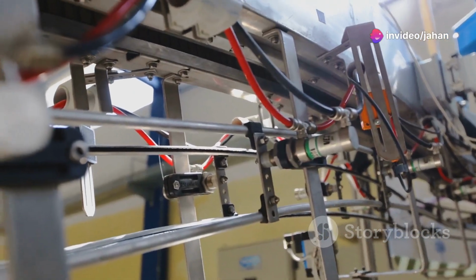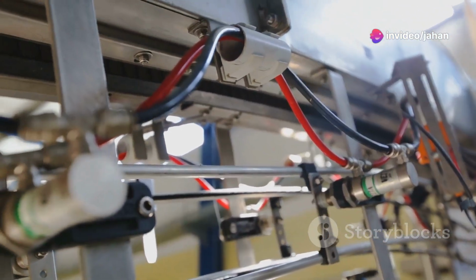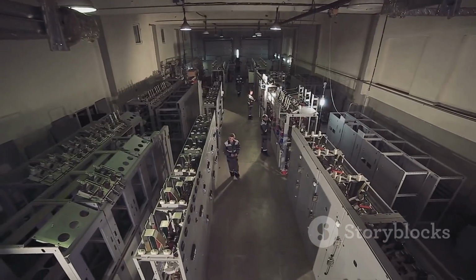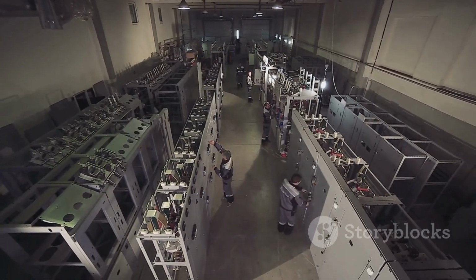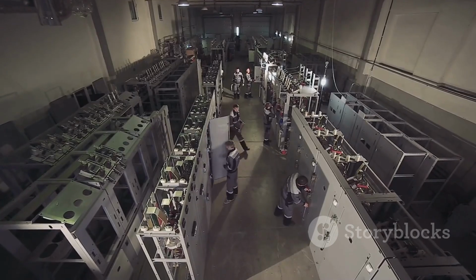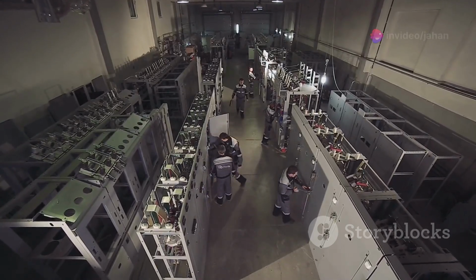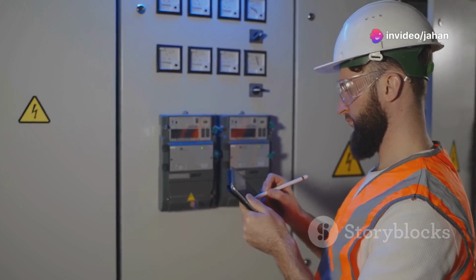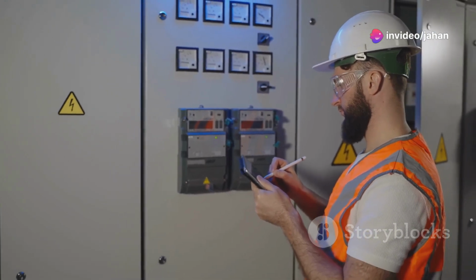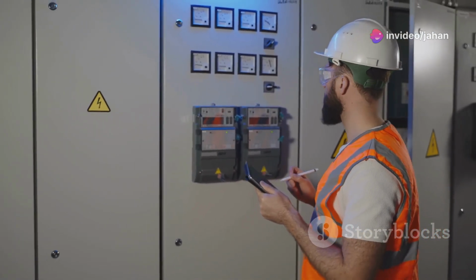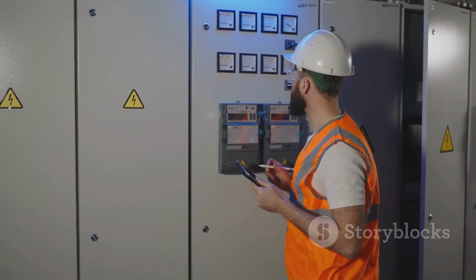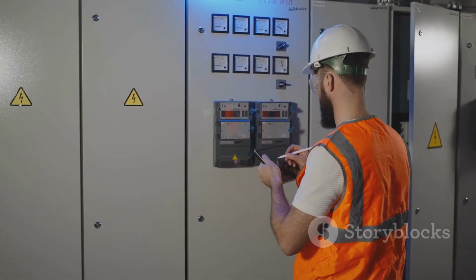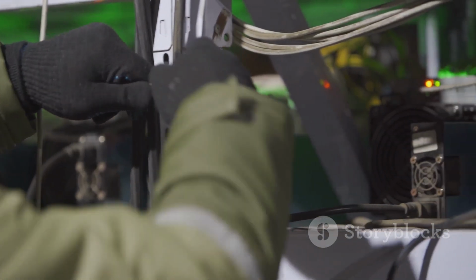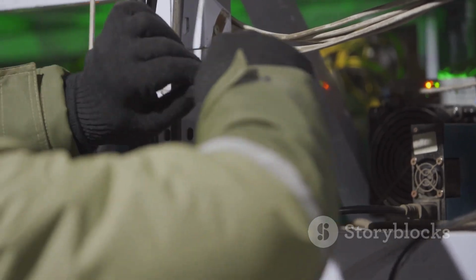Well, with ACBs, you can actually fine-tune this limit to match the specific requirements of your electrical system. This is crucial because different circuits have different capacities—for example, a circuit powering heavy machinery in a factory will have a much higher current rating than a circuit lighting your living room. By adjusting the overload current setting on the ACB, you ensure that it trips and interrupts the circuit only when the current exceeds the safe limit for that specific application. This level of customization ensures optimal protection and prevents nuisance tripping.